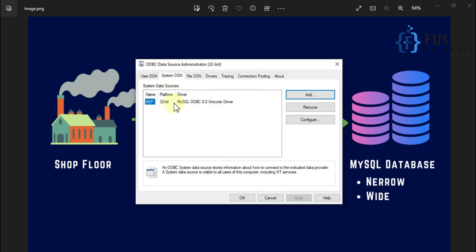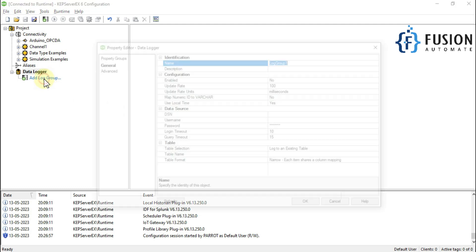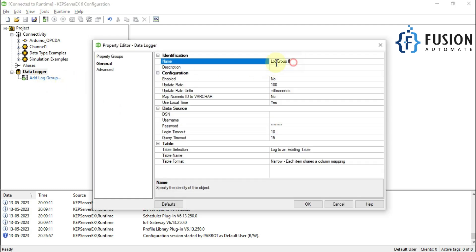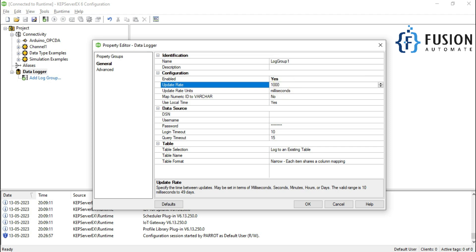We press the Test button to check the connection between our data source and the MySQL database. Press OK, then OK again. We have now created our MySQL ODBC data source and we are able to perform log operations from the KEPServerEX to MySQL database. Let me go to the KEPServerEX. Here we will add a log group — Log Group 1. Leave the name as it is and enable this log group. I want to update the log group every 1000 milliseconds, so I'll change the update rate.